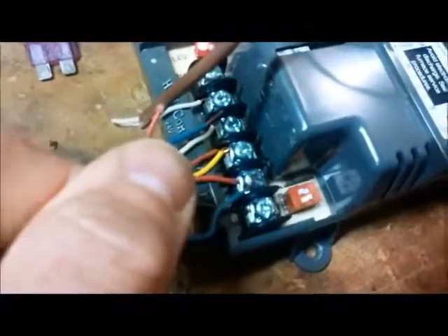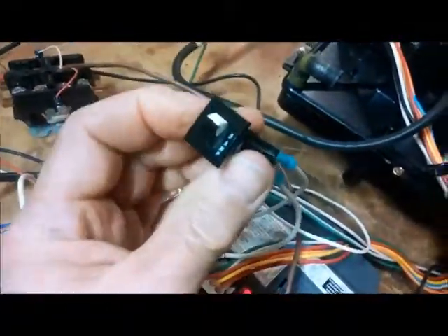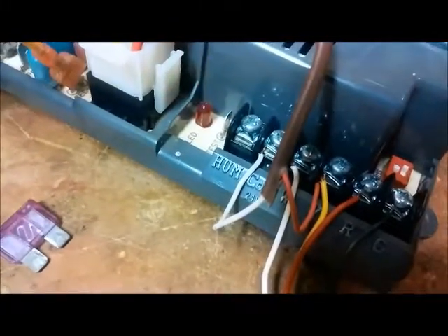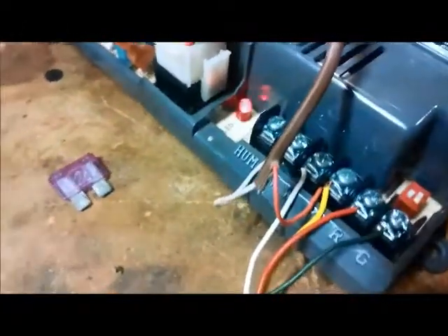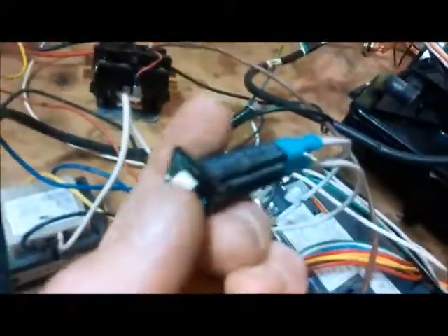let's try and show you short to ground. Okay, here's my wire. That would be just like jumping R to common here. And when we jump R to common or C, you'll see the breaker open. Right there, you just saw that little breaker. I've gotten places the fuse opened up. And we're getting a fault code. Getting a 2.4, secondary voltage fuse open. So I'll reset that breaker or replace our fuse, and we're back to steady on.